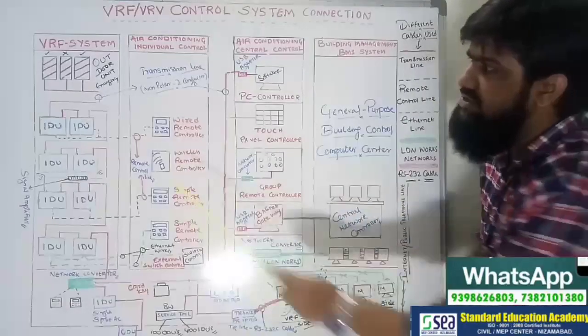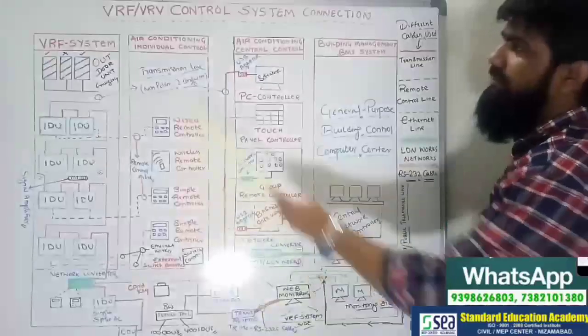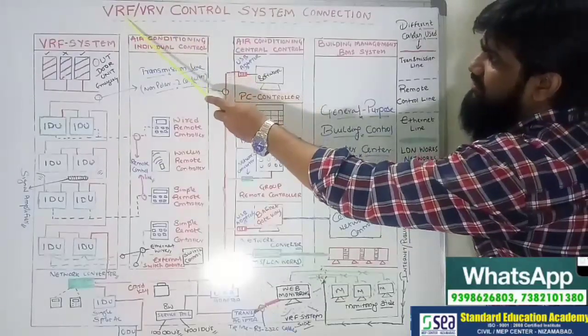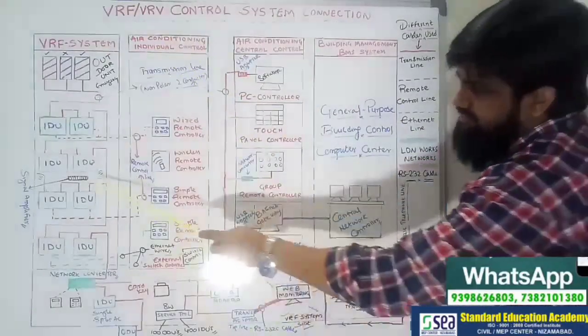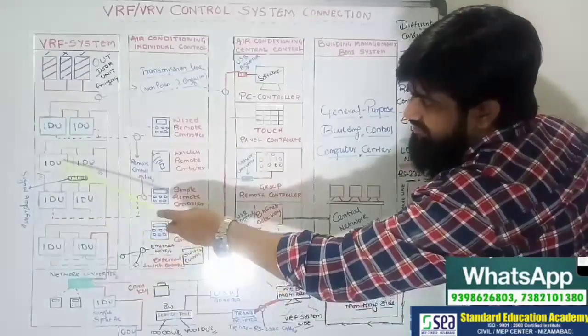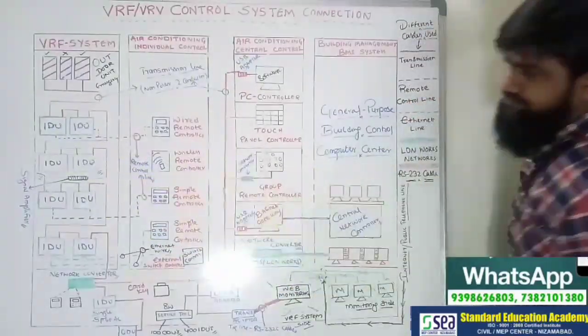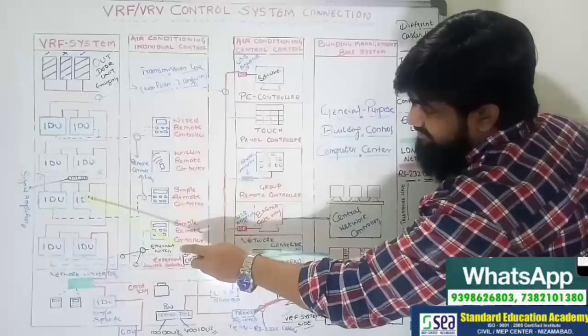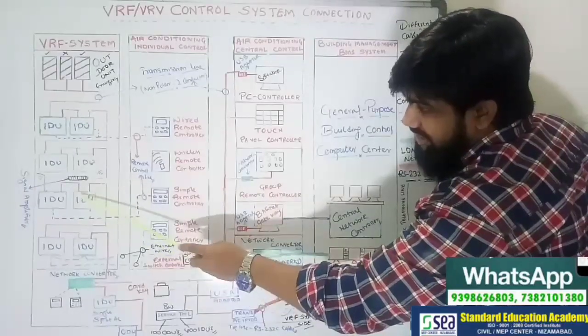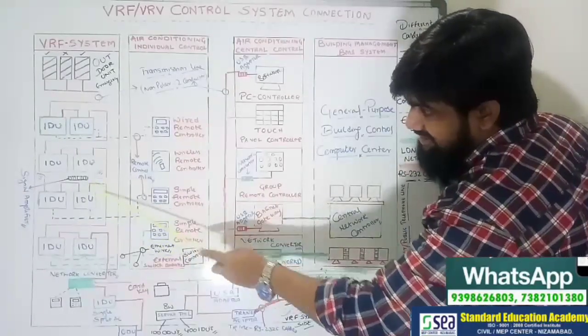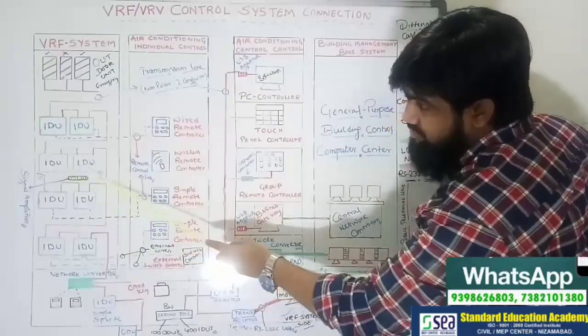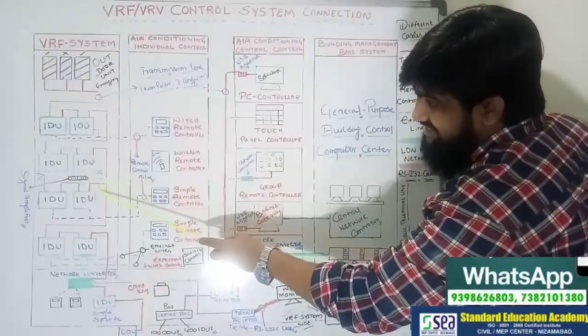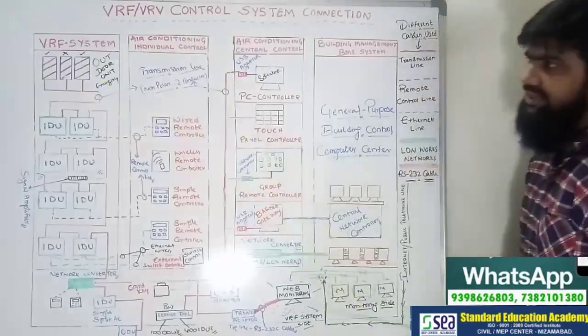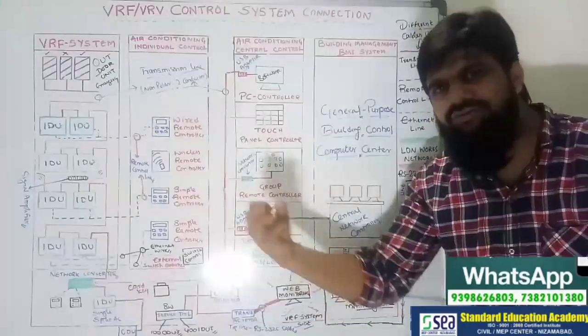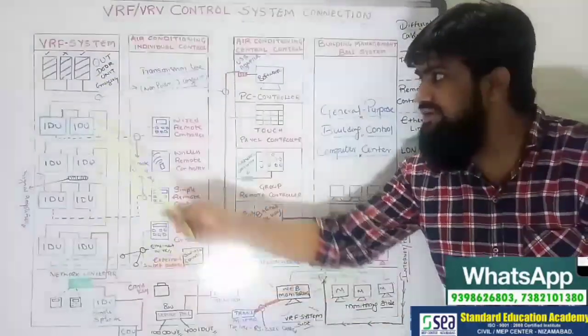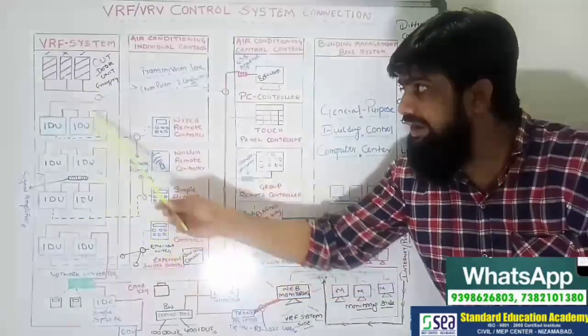Why do we need communication between outdoor and indoor? By the name itself, it's a variable refrigerant flow system. Every single IDU needs a different kind of refrigerant flow. Therefore, every single IDU, from its electronic expansion valve, sends a signal to the outdoor unit via this red transmission line wiring, stating how much refrigerant it wants. This signal is sent to the outdoor unit with the help of these wires.